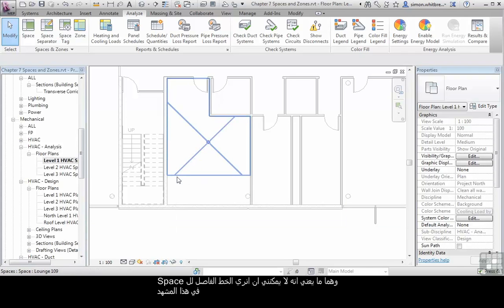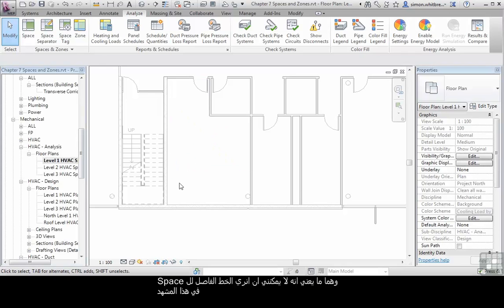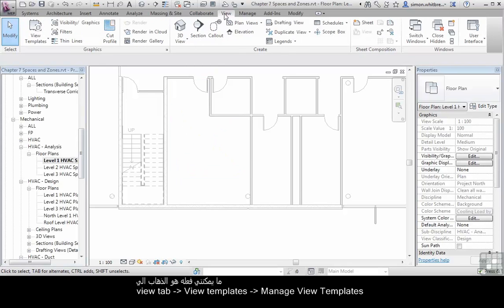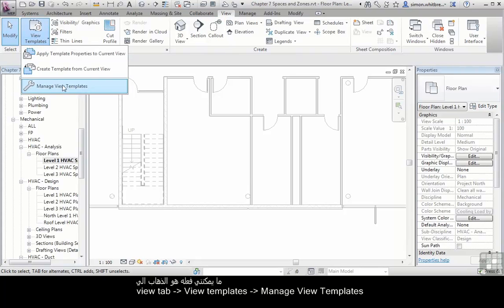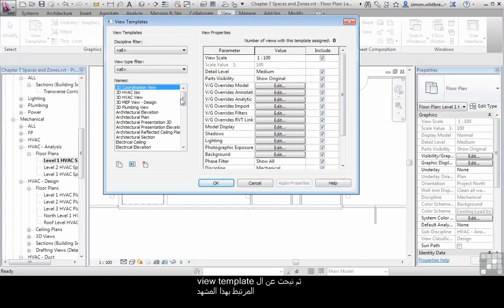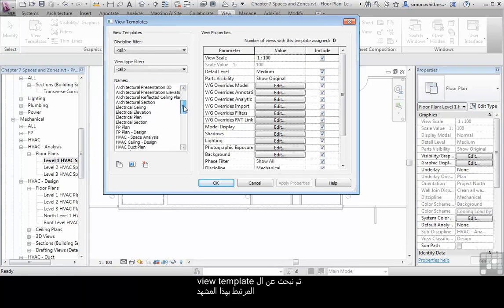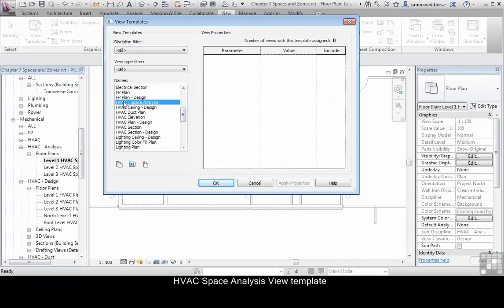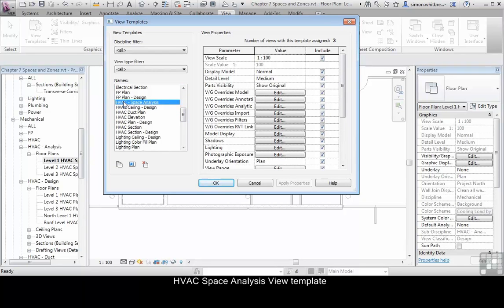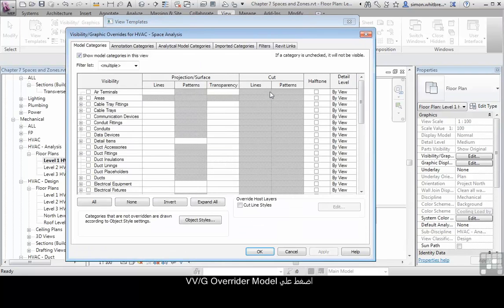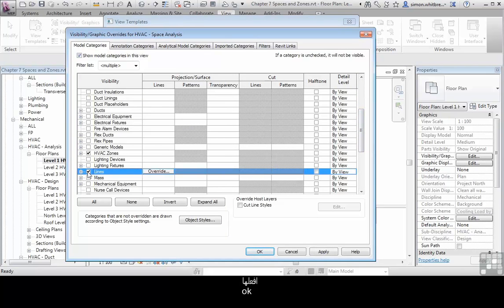What this means is that I cannot see the space separation line. What I could do is go to the View tab, click on View Templates, manage my view templates, and then look at the view template associated with this view. This is the HVAC Space Analysis view template. In here, I'll click on the visibility graphic overrides for model and scroll down until I find Lines. Turn them on and click OK.